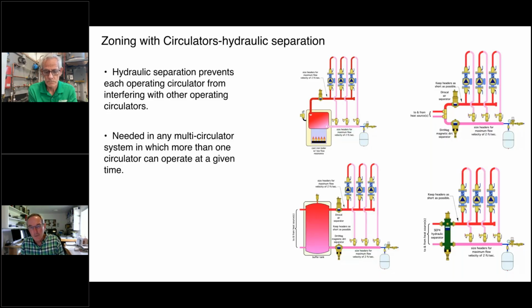But in general, when you had these larger headers and short headers and a cast iron boiler, you had hydraulic separation just inherent to the geometry of the system. You can do it with closely spaced T's like this. So if there's a circulator out here for a heat source, the closely spaced T's would isolate the pressure dynamics of the boiler circulator from the zone circulators.